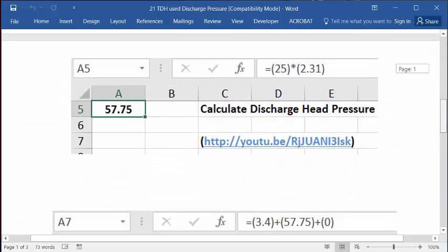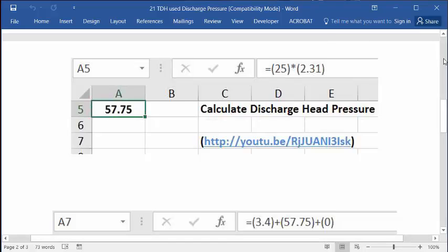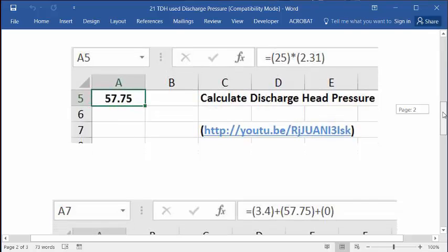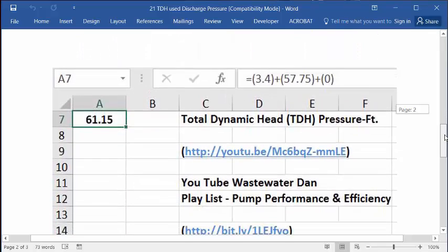This first one here is the original basic discharge head pressure formula which uses these numbers, the 25 and the 2.31. It's your answer 57.75. You can go to that link and you can see I have more explanation on that for your learning and training.